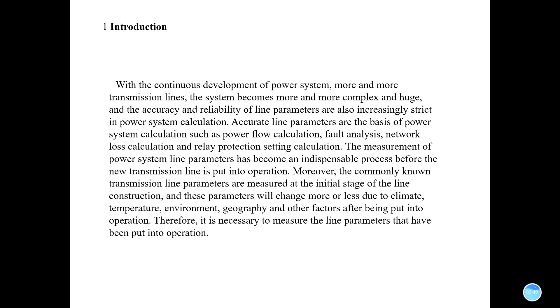Moreover, commonly known transmission line parameters are measured at the initial stage of line construction, and these parameters will change more or less due to climate, temperature, environment, geography, and other factors after being put into operation. Therefore, it is necessary to measure the line parameters of lines already in operation.